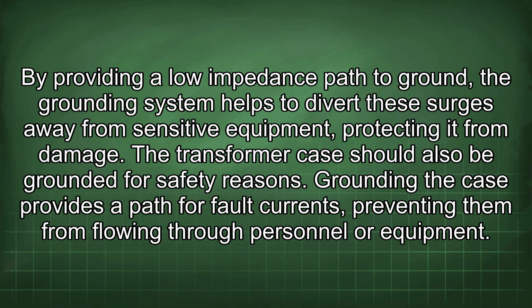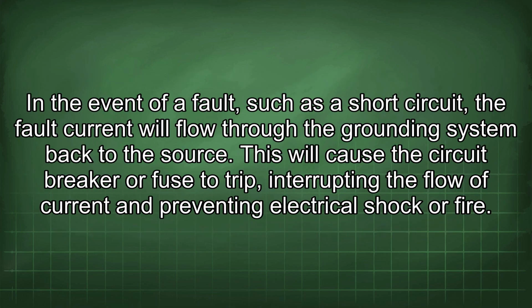Grounding the case provides a path for fault currents, preventing them from flowing through personnel or equipment. In the event of a fault, such as a short circuit, the fault current will flow through the grounding system back to the source. This will cause the circuit breaker or fuse to trip, interrupting the flow of current and preventing electrical shock or fire.